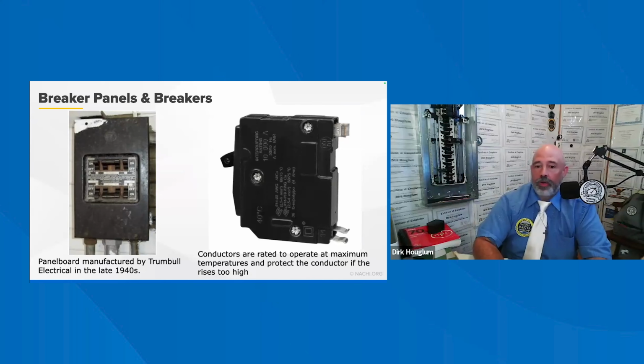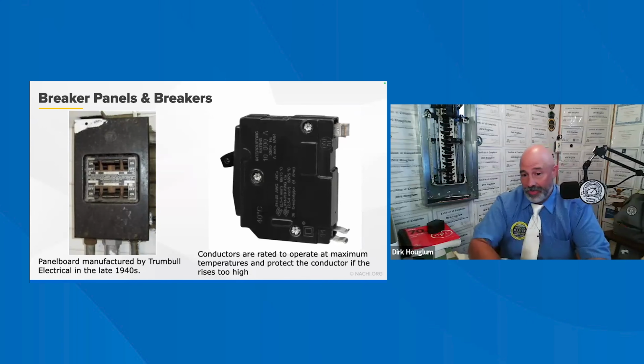Code requires that the overcurrent protective device, like a circuit breaker or fuse, be installed in series with each ungrounded conductor, the hot wire, at the point where the conductor receives its supply inside the panel board, except for service entrance conductors. So circuit breakers fall into 4 categories.